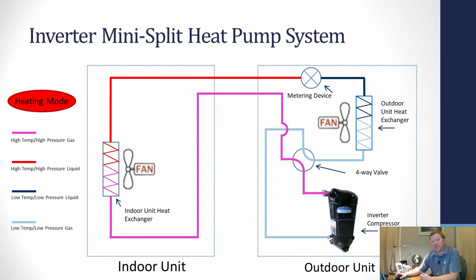So on a traditional heat pump system, you typically have to lock out your heat pump when it gets cold outside, because they just can't efficiently heat your house when it's cold outside. That's why you have backup heat. That's why you have gas furnaces or electric strip heat or baseboard heaters or cadet heaters or fireplaces or something else. When you go to an inverter heat pump, between the compressor, the variable speed fans, and the electronic expansion valve, we now have way more controls and ability to heat at lower outdoor temperatures.